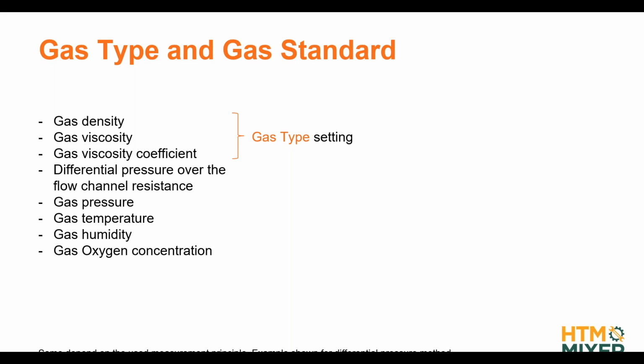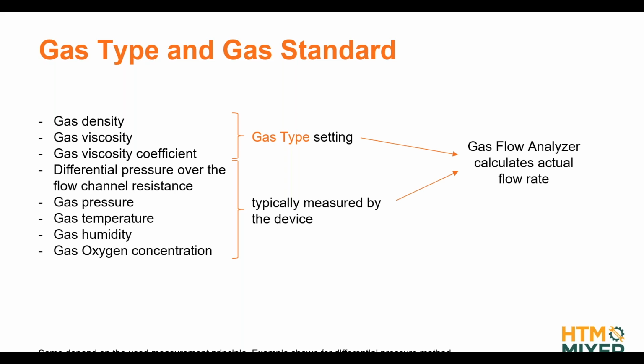And all the other things are typically measured by the gas flow analyzer. So there's something to be measured actually. In our example here, this is for differential pressure measurement, gas flow analysis. There are other principles out there, but typically you have something that actually determines the flow rate itself, but then you also need to know the gas pressure, gas temperature, humidity, and also very typically the concentration of oxygen. And these are all things that are typically being measured by the gas flow analyzer. So we have a setting and we have measurements, and all that actually combined lets the gas flow analyzer calculate the flow rate of the gas that is actually passing through the gas flow analyzer. And let's consider this gas flow measurement. Okay, so we always measure the actual conditions.